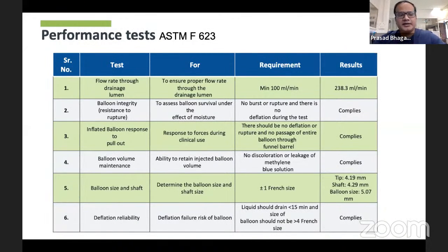In this particular guideline, there are 6 different tests, of which the first is the flow rate through the drainage lumen. As you know, different sizes of catheters have different urine flow rates. The flow rate is very important, because the primary aim of using a catheter, that is the intended use, is to drain the urine. And imagine if the flow rate is not as per the standard guideline, that means your device is not performing the function it is intended to do. That's why the flow rate is very important, and we have ensured that our flow rate matches the requirement of the ASTM guideline.